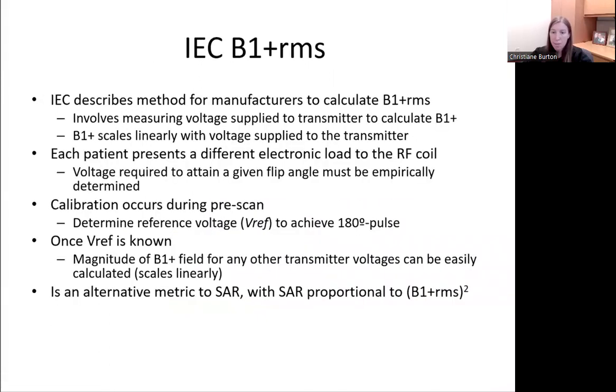The IEC describes a method by which manufacturers may calculate B1 plus using the principle that B1 plus scales linearly with voltage supplied to the transmitter. However, because each patient presents a different electronic load to the RF coil, the voltage required to attain a given flip angle must be empirically determined. This calibration occurs during pre-scan, where 1 millisecond rectangular pulses of different amplitude are tested until the reference transmitter voltage, Vref, to achieve a perfect 180-degree pulse is determined. Once Vref is known, the magnitude of the B1 plus field for any other transmitter voltages can be easily calculated.